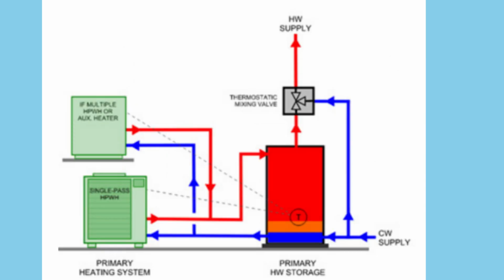No recirculation systems. In some buildings, if the fixtures are close enough to the water heating plant, you don't need a domestic hot water recirculation loop at all. This is the simplest, most efficient design. It eliminates return water issues and pumping energy. It's especially effective with single-pass and integrated heat pump water heaters.